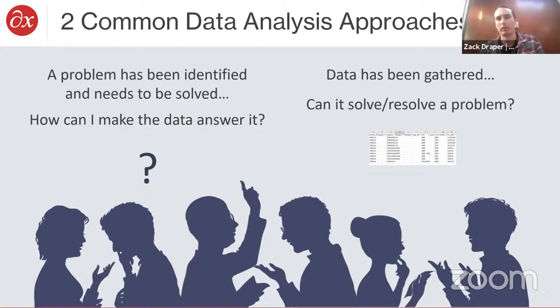On the other hand, you can do a bottom-up approach where you look at the data and you see what does the data actually tell you. Does DGA correlate with the reliability or not? It may be that you're measuring something that has no relationship to whether or not the transformer is serviceable or not. And the only way you understand that is by actually looking at the data instead of trying to impose some assumption that this data set is going to tell you something about the problem that you're trying to solve. The downside with the bottom-up approach too is that you may spend a lot of time searching through the data to try to find something useful, and you may come up with nothing. So you may not end up solving the problem that you set out to solve.